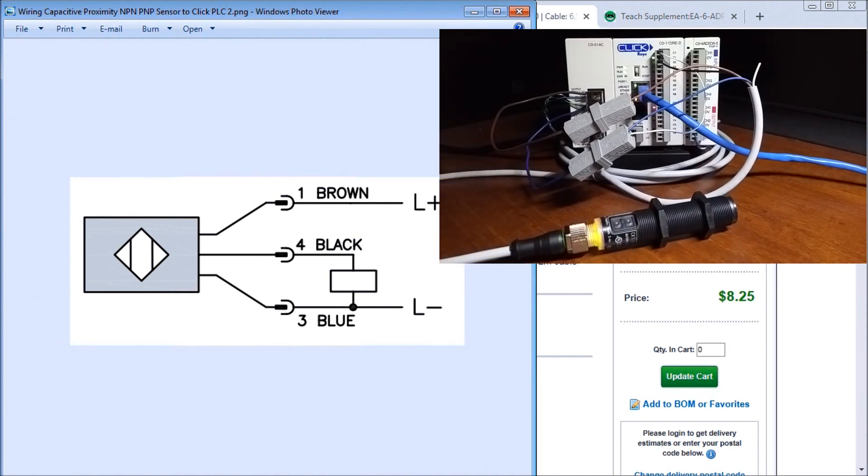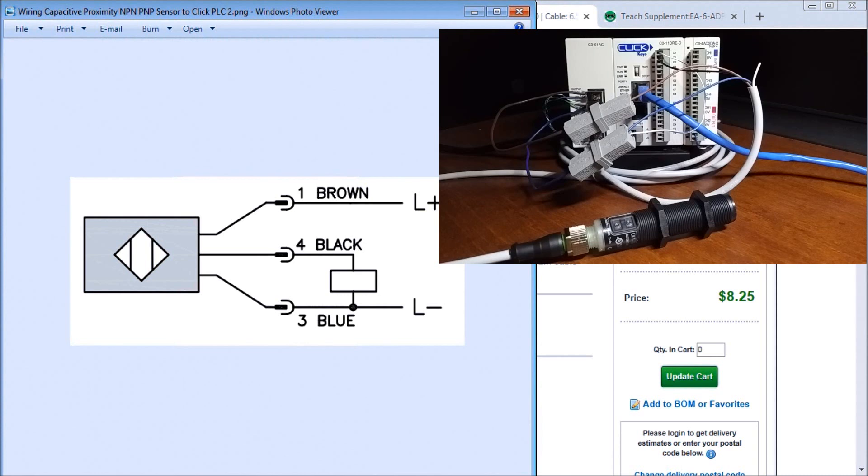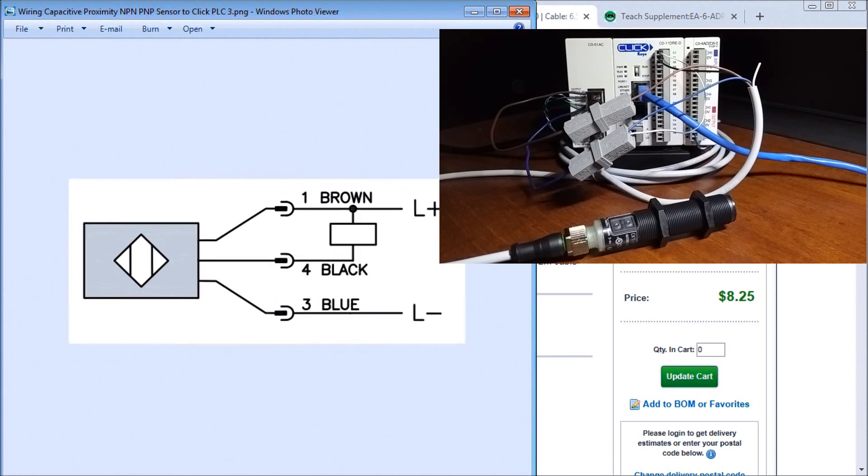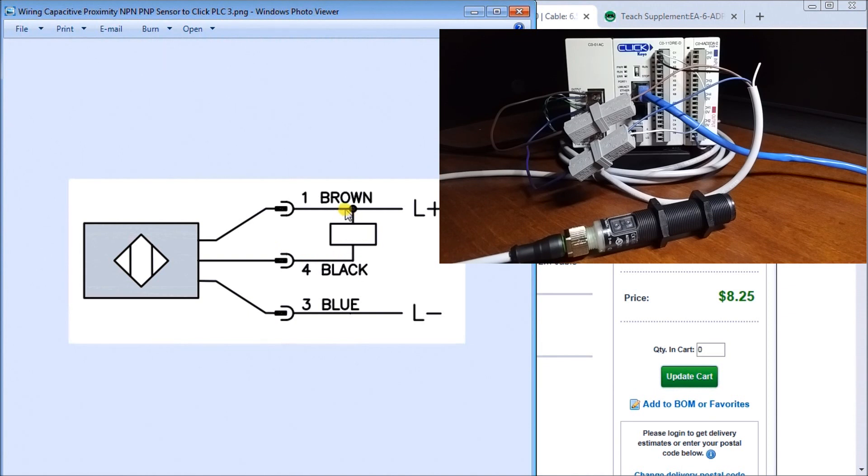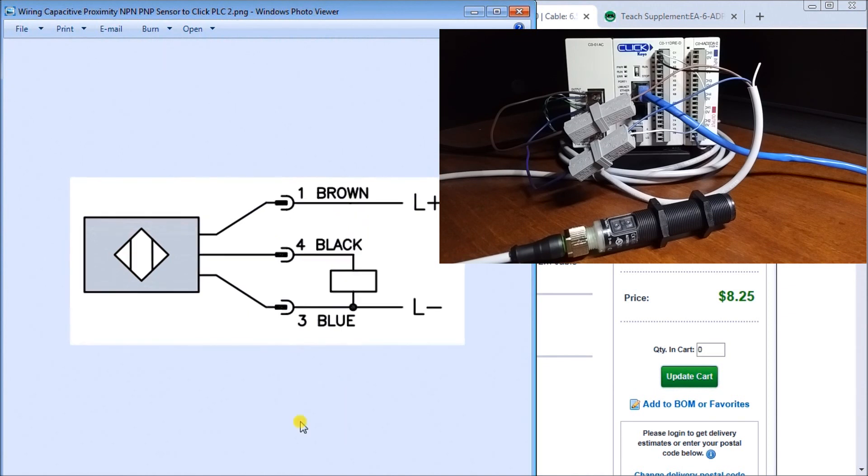Now let's change that wiring to negative switching or sinking the load. In order to do that you'll see my black wire really stays the same as my input and my load now appears between my brown and my black wire as opposed to my load appearing between my black and my blue.